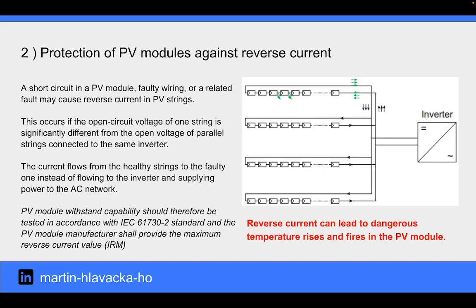A short circuit in a PV module, faulty wiring, or a related fault may cause reverse current in PV strings. This occurs if the open circuit voltage of one string is significantly different from the open circuit voltage of parallel strings connected to the same inverter. The current flows from the healthy strings to the faulty one instead of flowing to the inverter and supplying power to the AC network. Reverse current can lead to dangerous temperature rises and fires in the PV module.